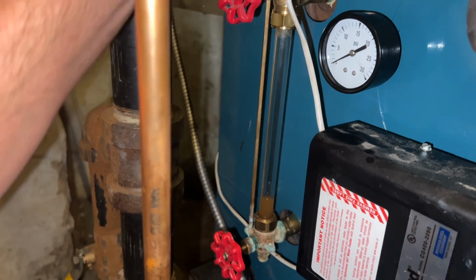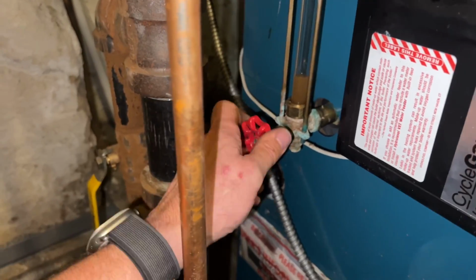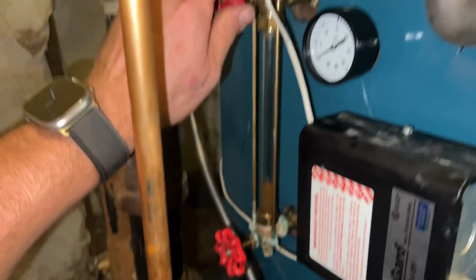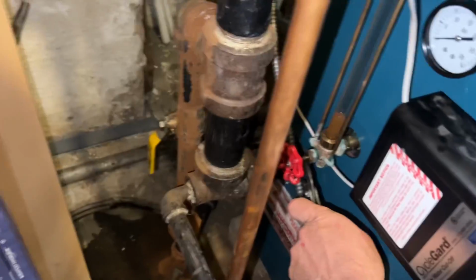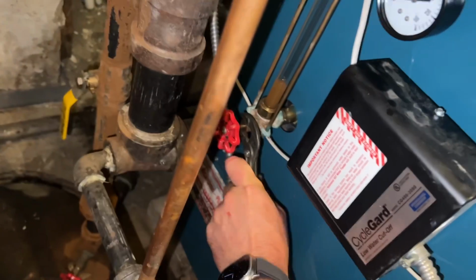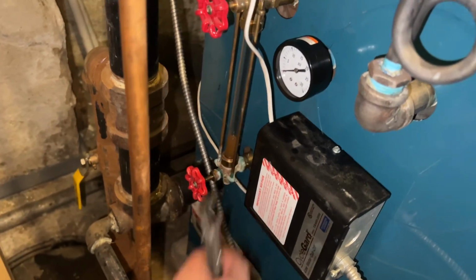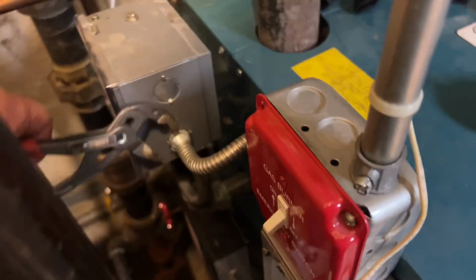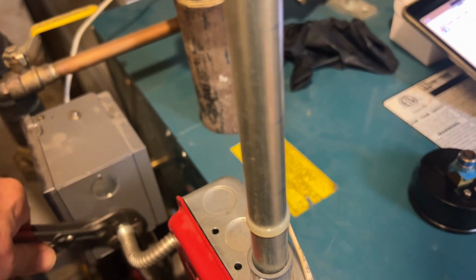Okay. Let's put our gauge glass back in. Our valve. Make sure that's open, top and bottom. You need an upper valve. Otherwise, you won't get a good sense of water level, because it's airbound there. So you need upper and lower valves open. There's our water level right there. Looks pretty good. All right, next I'm gonna remove the wiring for the pressuretrol.